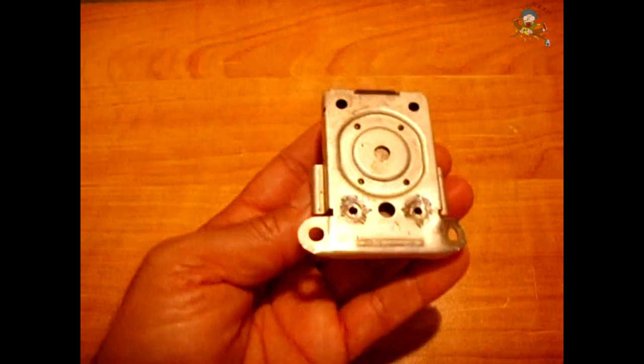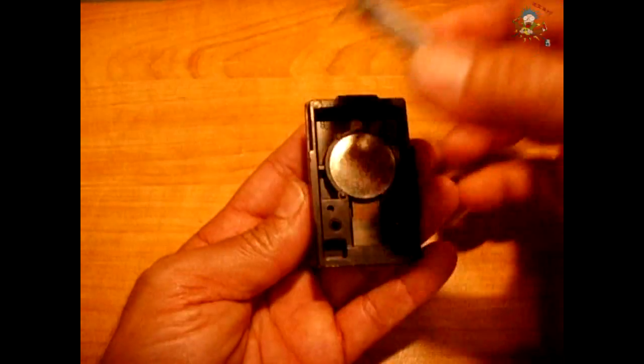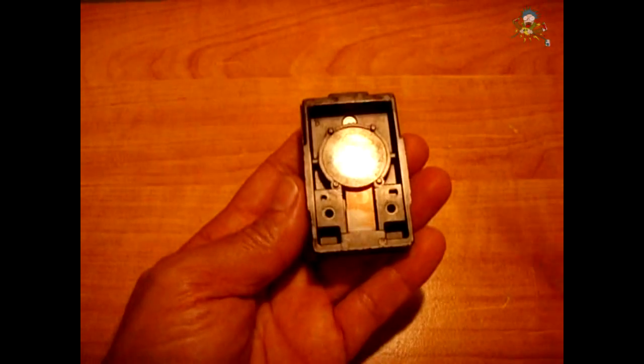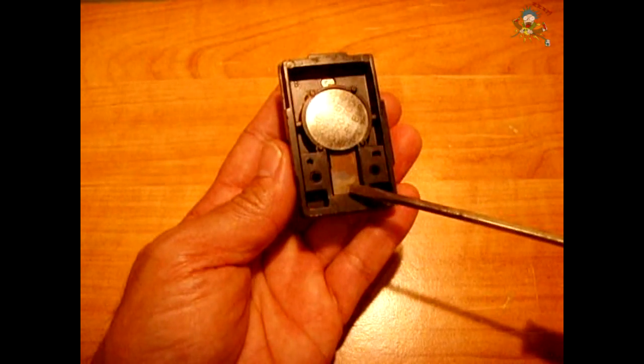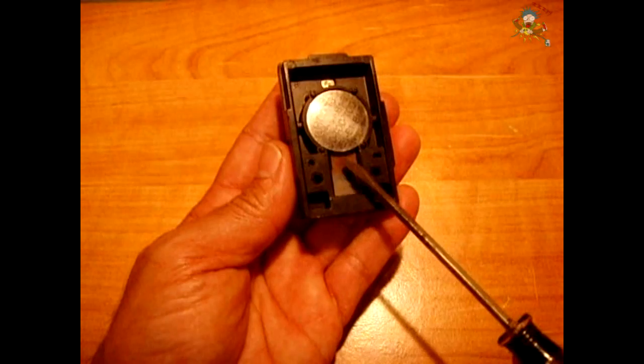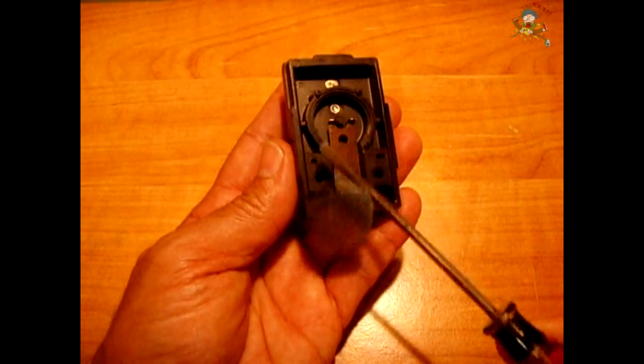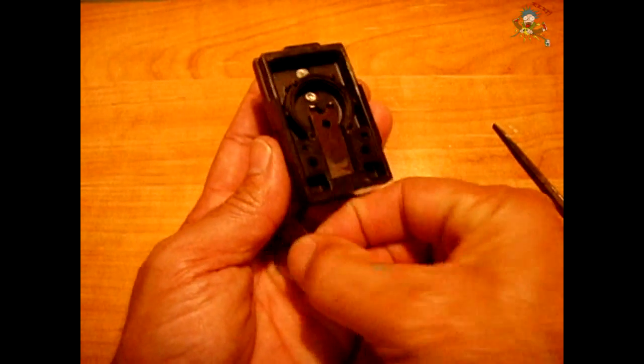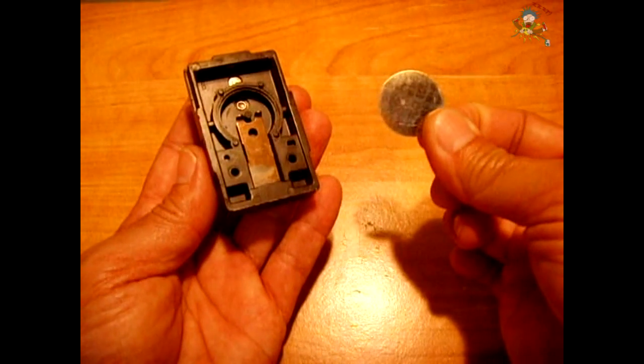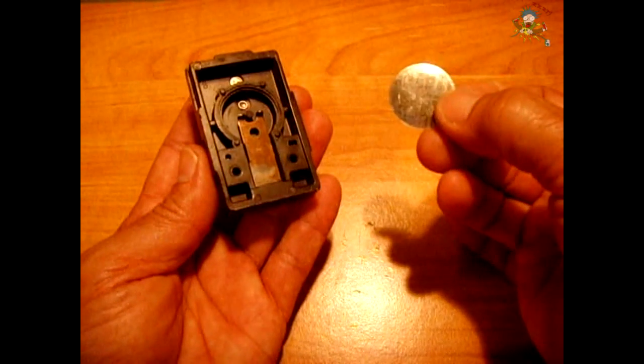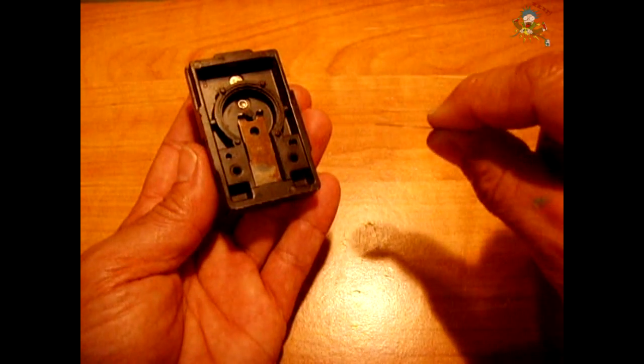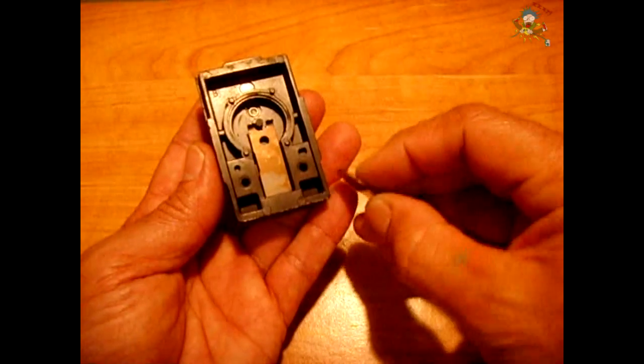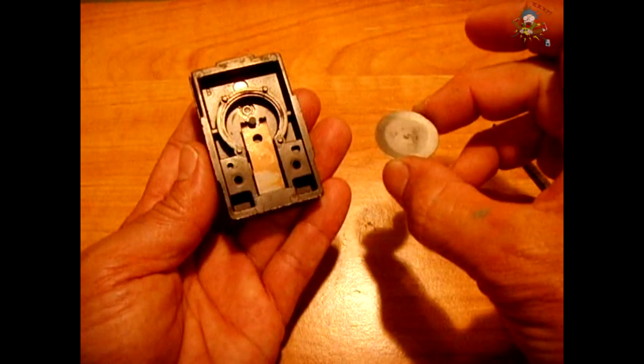Remove the back plate. Now the first thing you're going to see is this disc and then there's this metal plate. Let's pop out the disc. Now what this is is nothing more than a bi-metal disc. It's made up of two dissimilar metals that are bonded together as one and it's slightly cupped.